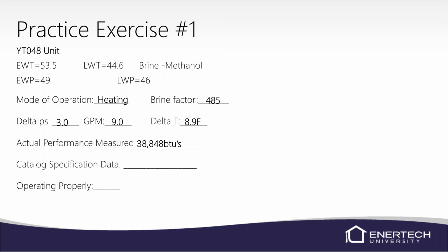So now we know what we measured, 38.8. The catalog's at 39.6. So are we within 10% of what the catalog recommends? Yeah. We're actually probably moving a little bit more than the 9 GPM. We're probably moving about 9.5 GPM, and that would probably put us right at the number, because we are actually at 3 and not at 2.9 on our pressure drop. But this gives us close enough. 10% of 38,800 is about 4,000 BTUs. So as long as we're under or over 35,600 BTUs, then we're within our 10%. So yes, this unit is operating properly.